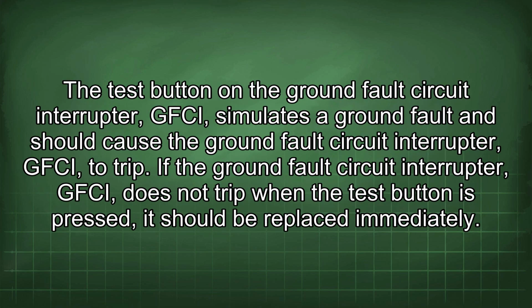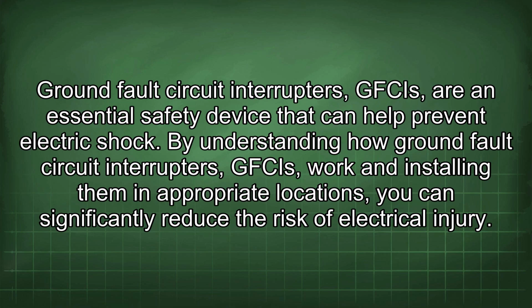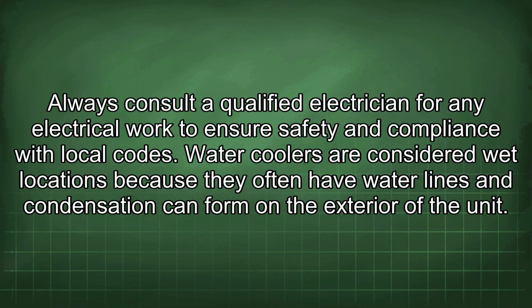The test button on the GFCI simulates a ground fault and should cause the GFCI to trip. If the GFCI does not trip when the test button is pressed, it should be replaced immediately. GFCIs are an essential safety device that can help prevent electric shock. By understanding how GFCIs work and installing them in appropriate locations, you can significantly reduce the risk of electrical injury. Always consult a qualified electrician for any electrical work to ensure safety and compliance with local codes.